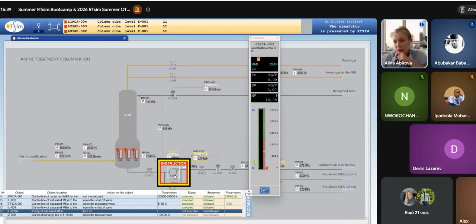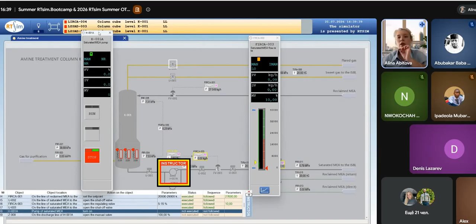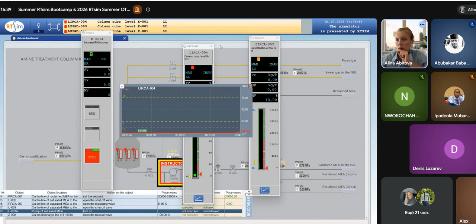But here there is a point and the idea why we can't always and every time simply follow the instructor. Why? In order to turn on the pump, there must be enough liquid in the column cube. But we see that the amount of raw material in the column is very, very small. As you can see right now, it's like 3%. So the pump will have nothing to pump out, and this can lead to an emergency, and we need to wait till it will be at least 45-50% to ensure smooth opening of the pump.